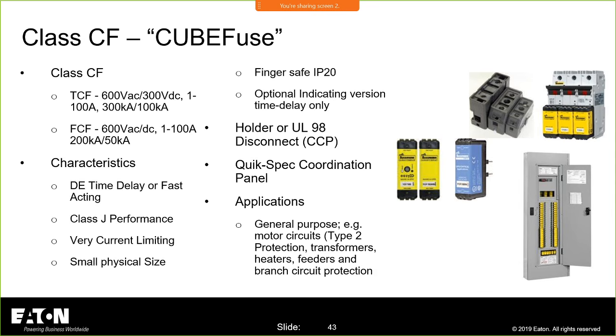Class CF cube fuse. This one was designed, basically, to take the class J performance. So if you understand the class J fuse curves, you'll understand the fuse curves for the class CF. They offer a time delay or fast acting. Again, it's class J performance. Very current limiting, small physical footprint, and the value prop on this one is right here in this panel. We use a lot of these in selective coordination in your Article 700 systems for industrial and commercial power systems.